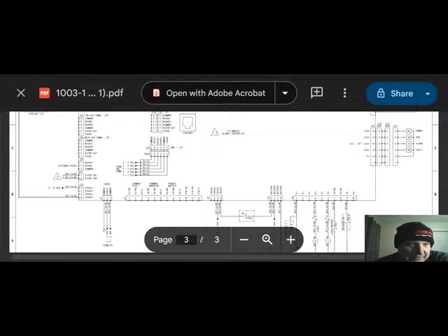How you tie this in is going to depend greatly on how you're integrating this. Is this something where you have a system that looks for an input and then alarms when that input goes away, or does it look for an input not to be there and then alarms when that input comes? If it's a light that's on, and if you have this rigged up to a light or something, is that going to be looking for power on fault? So that's what you got to figure out beforehand, is knowing exactly what you're tying into with this and what kind of signal it's going to be looking for.